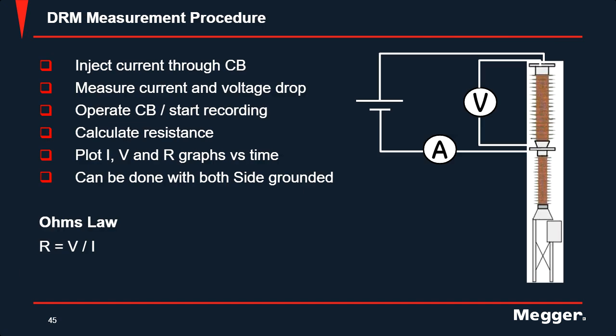So how does this work? It injects the current into the circuit breaker, and it measures the current and voltage drop as the circuit breaker operates, and then starts recording. Once that pulse signal gets to your open or your close coil, it starts the timer, and then it calculates the resistance, and then plots your current, your voltage, and your resistance versus time. And again, this can be done with the dual grounding technique. It's as simple as Ohm's law.